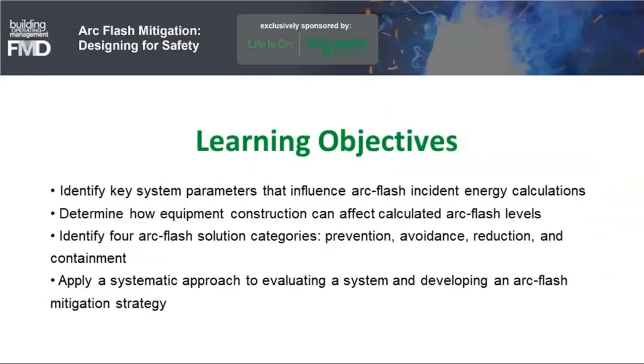In today's webcast, our learning objectives include identifying key system parameters that influence arc flash incident energy calculations, determining how equipment construction can affect calculated arc flash levels, identifying 4 arc flash solution categories: prevention, avoidance, reduction, and containment, and applying a systematic approach to evaluating a system and developing an arc flash mitigation strategy.